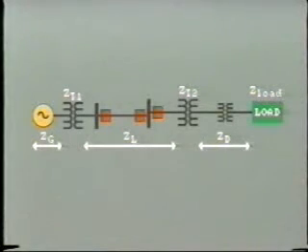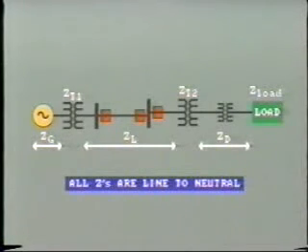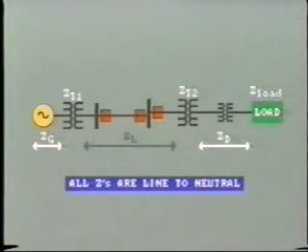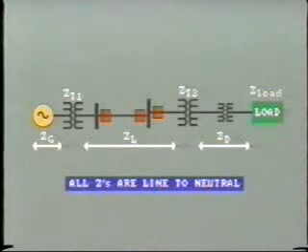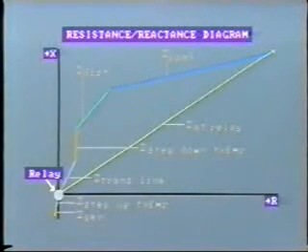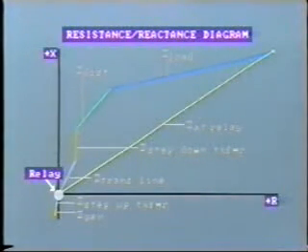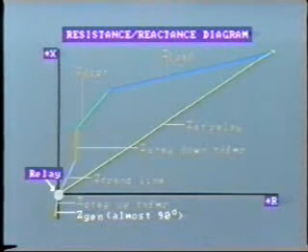Let's take our study a step further now and consider the magnitude and phase angle of the various impedances. Here is another single line diagram, but this time of a more complicated system. The impedances line to neutral are represented here: the generator, the step up transformer, the transmission line, the step down power transformer, and here the total distribution circuit including the distribution transformer, and eventually the impedance of the load. Now let us plot on a resistance reactance diagram the impedance as seen by a relay located after the generator step up transformer. First, we have the impedance of the generator — this is quite a low value and consists mainly of reactance, as can be seen from the large phase angle.